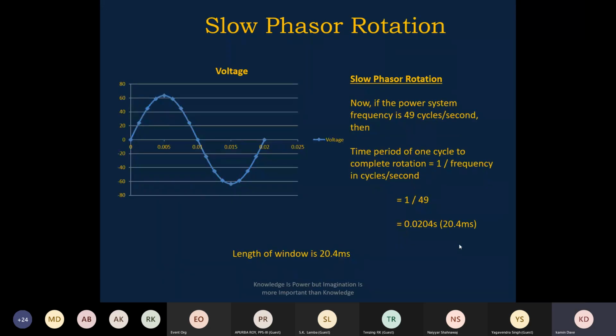Okay, so slow phasor rotations. Most of the time when we do synchronization, the wording phasor rotation is most common. Let us say the phasor rotation is fast or slow. Then when we test relays, specifically under frequency relay testing, over frequency relay testing or df/dt relay testing, we have frequency terms such as 49.5 hertz or maybe 50.5 hertz. So what does this mean? Frequency is associated with phasor rotations.